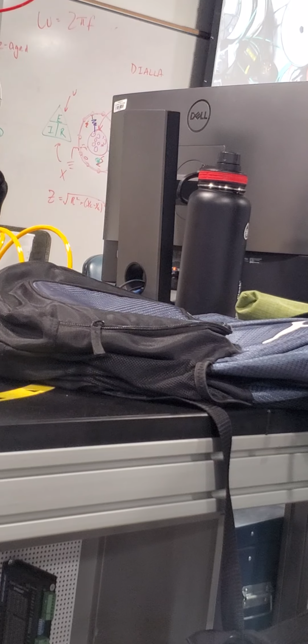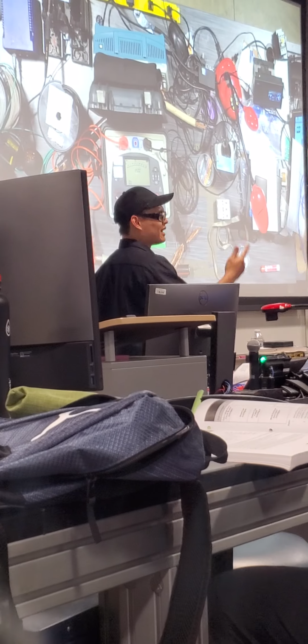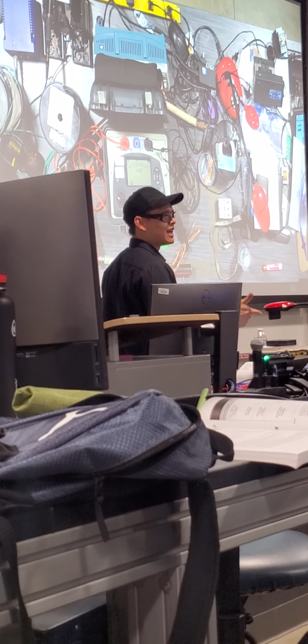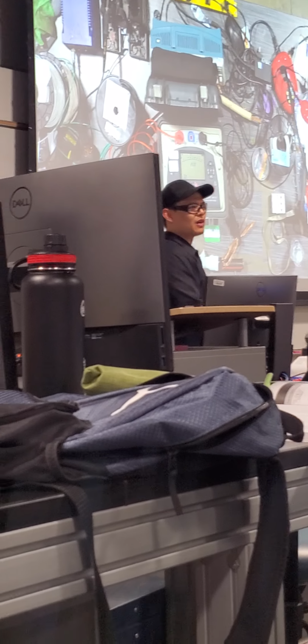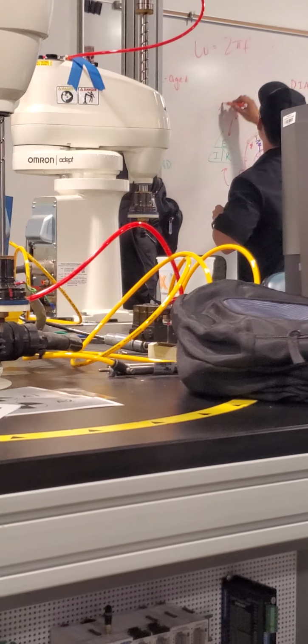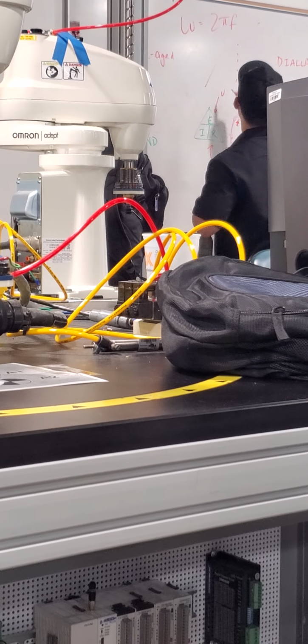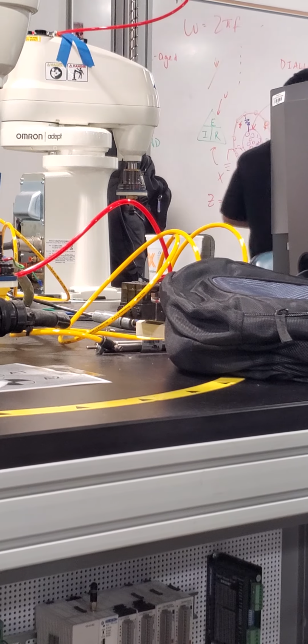So you're the next guy. If I test it in 60 seconds, now we all have a standard we can agree on. So when the next person comes in, they can also test in 60 seconds so that we're actually comparing apples to apples, right? Because if we know the insulation curve goes like this, unless we're all testing at the same point, how do you know it's not a lower reading because you didn't test long enough?